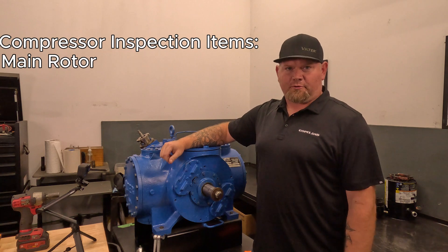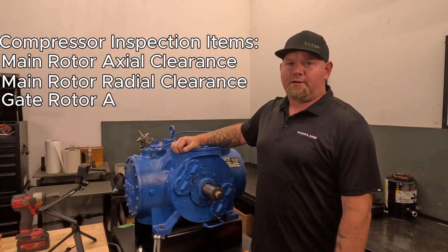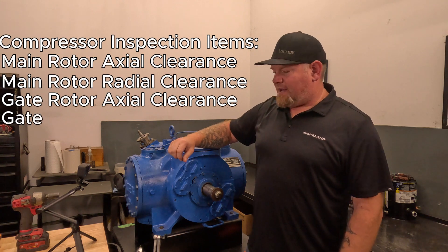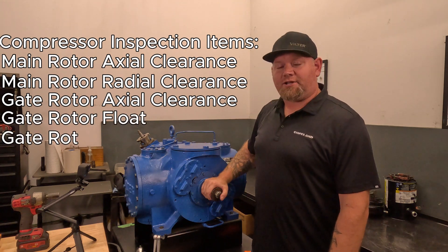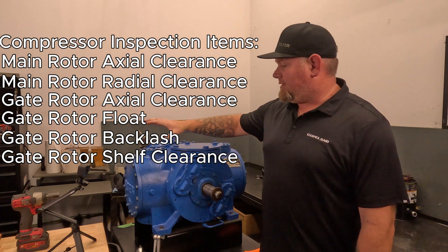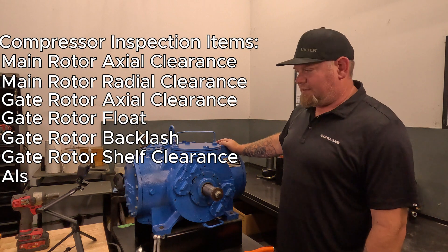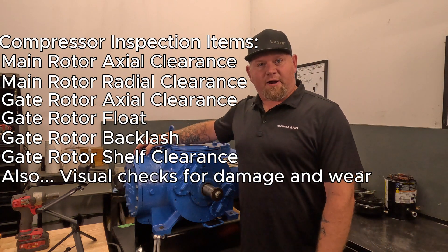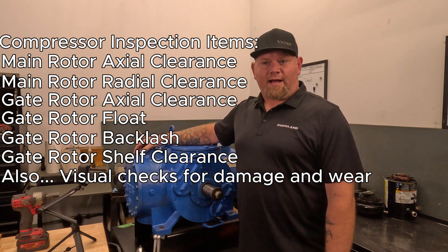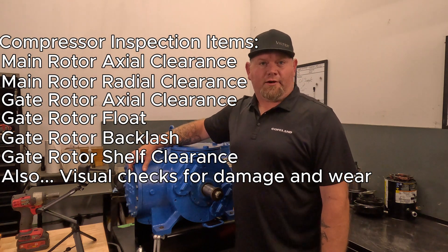Regular maintenance of your Vilter screw compressor is going to consist of a regular annual inspection of the machine. We recommend that the bearings get checked — that's going to be axial and radial end play on your main rotors, as well as each of your gate rotors. These gate rotors will be inspected for bearing play, gate rotor wear, bushing wear, and shelf clearances.